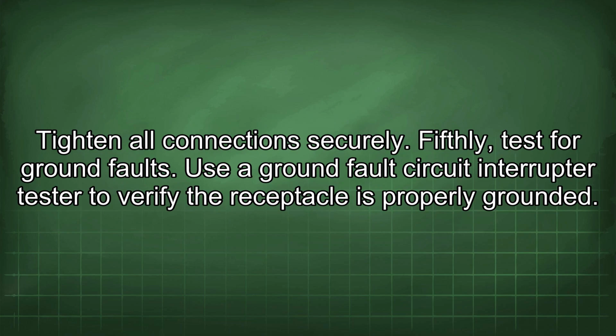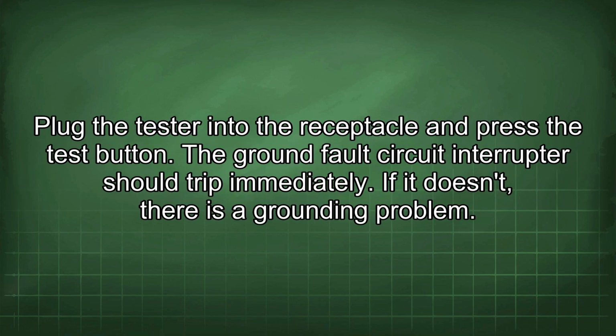Tighten all connections securely. Fifthly, test for ground faults. Use a ground fault circuit interrupter tester to verify the receptacle is properly grounded. Plug the tester into the receptacle and press the test button. The ground fault circuit interrupter should trip immediately. If it doesn't, there is a grounding problem.